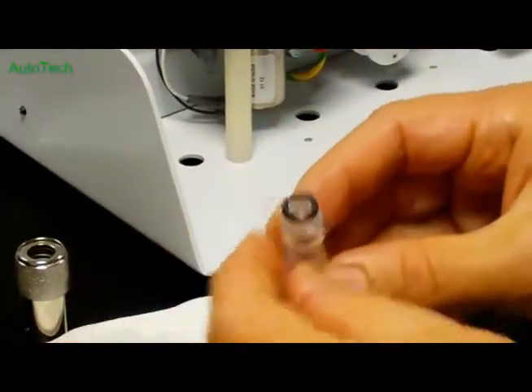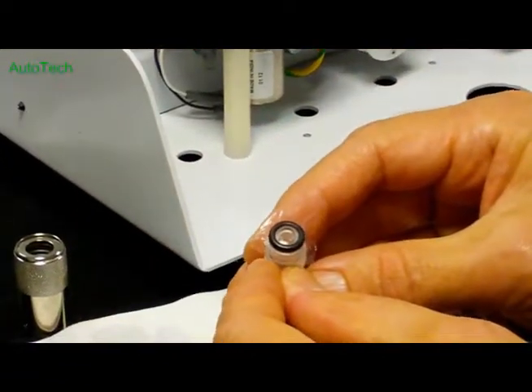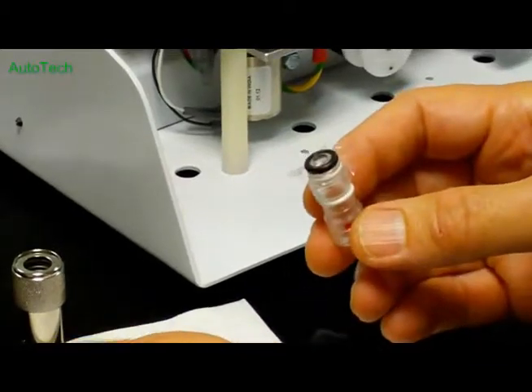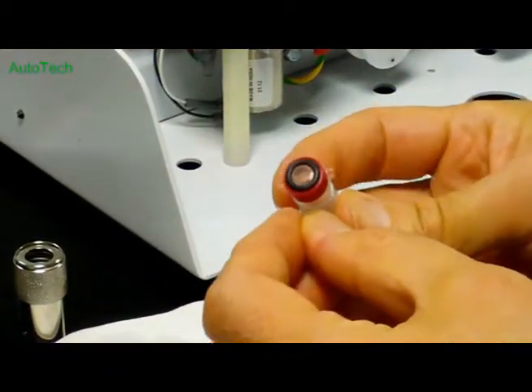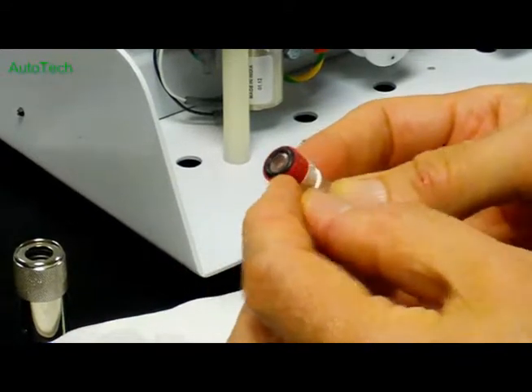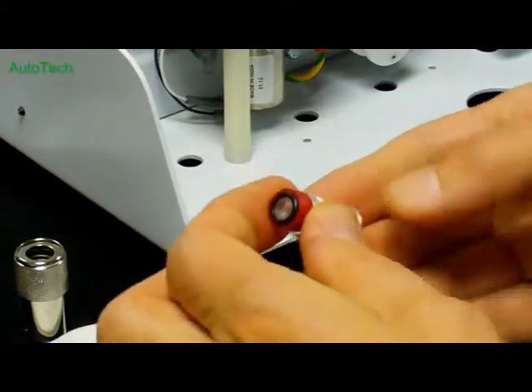So if you have a quick look at the membrane, you can see the membrane is perfectly flat. Now we can put the red crown in place. Just, that retains the membrane mounting ring better.